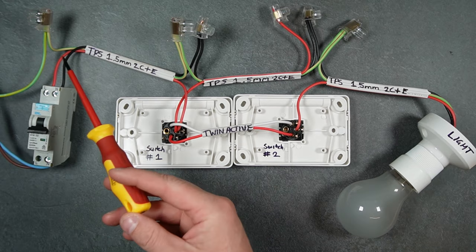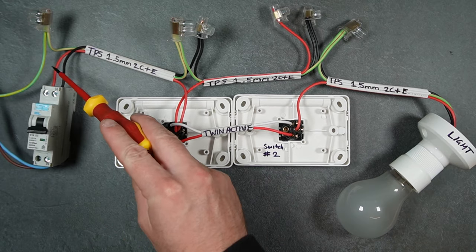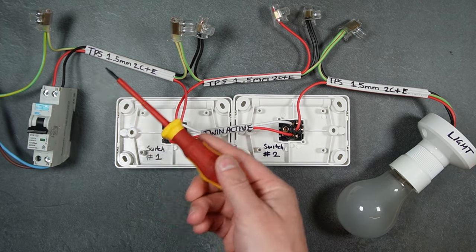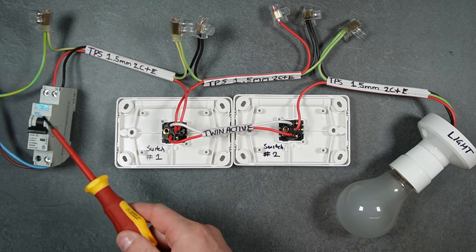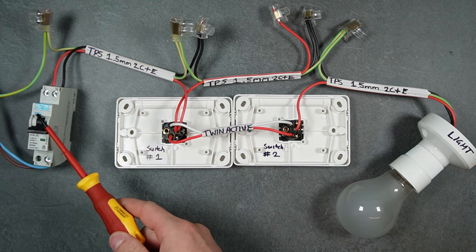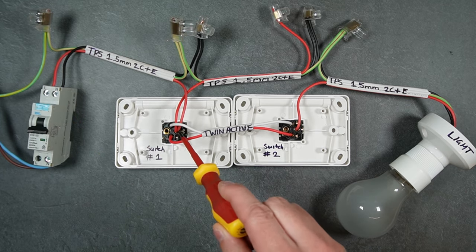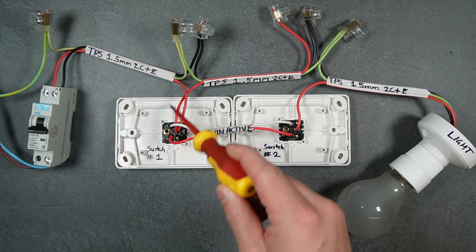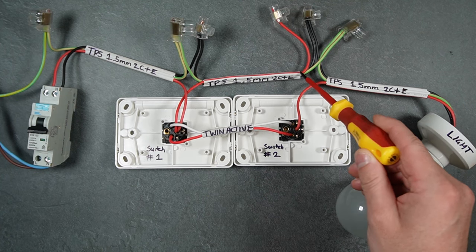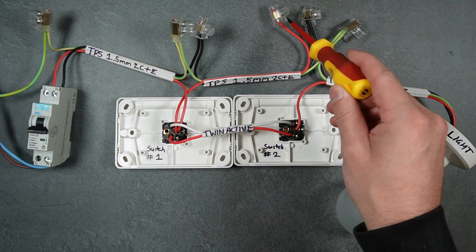At the start of the circuit, the red active is called a hard active, and that's because it always has power on it unless it's isolated from the switchboard. The hard active will go into the common of switch number one and join with another active that goes over to switch number two, and it'll go into a connector.